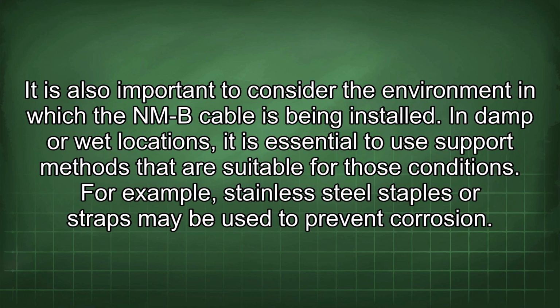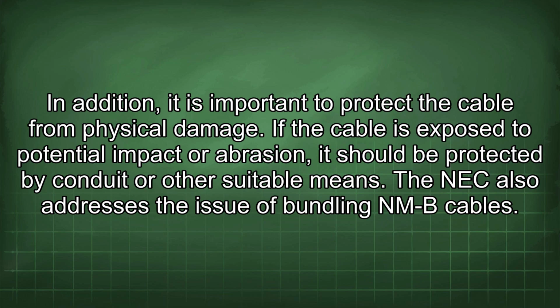It is also important to consider the environment in which the NMB cable is being installed. In damp or wet locations, it is essential to use support methods that are suitable for those conditions. For example, stainless steel staples or straps may be used to prevent corrosion. In addition, it is important to protect the cable from physical damage. If the cable is exposed to potential impact or abrasion, it should be protected by conduit or other suitable means.